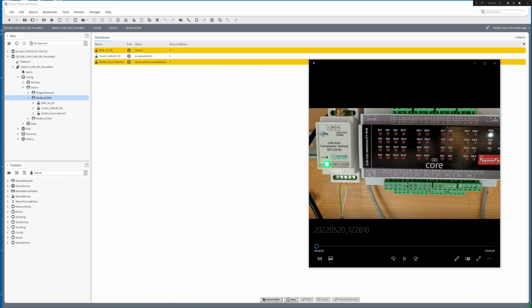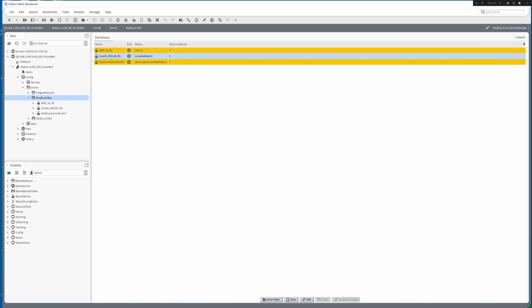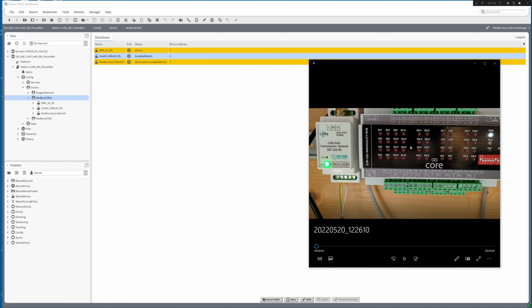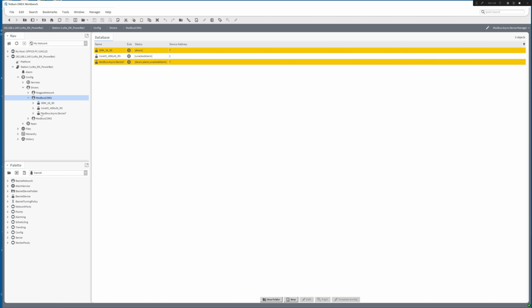This was my other configuration. I found out what the issue was. I unplugged the USB and plugged it back in again, and it worked. So I programmed up this one, and then I moved these wires to A2 and B2 on both modules, and we are communicating now to the Core 40 multi, which is this device here. So we can now look at some points.